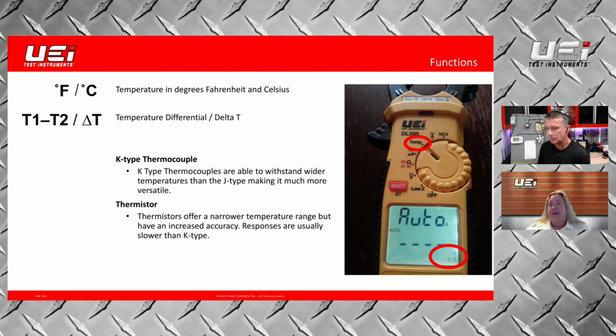A good check, though, is if for some reason you've managed to reverse that polarity: a quick thing you can take a look at is if you're putting it on something that you know is supposed to be cold and you see your temperature going up, that's a good sign you've reversed your polarity. Some meters won't give you a reading at all, but a lot of times it's very common that you're going to see your reading going in the opposite direction of what you're looking for.